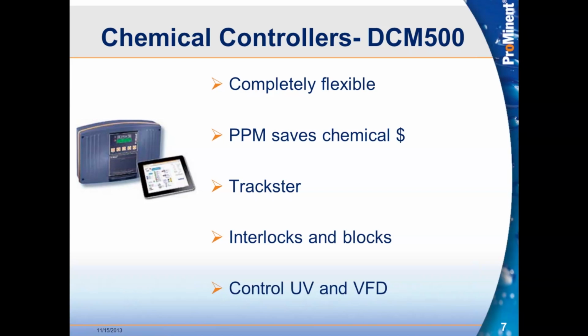Trackster auto poll allows us to, basically, I don't know if there's an upper limit, but let's say we have 30 controllers scattered across a metro area. Trackster running in the background on a computer somewhere can simultaneously watch all those controllers and reach out and grab a data packet as often as you want, and pull that data into the Trackster database. That does a few things for us. It helps us take electronic logs, to simultaneously watch 30 pools at the same time. Trackster can also text out and email out alarms, so that if something is occurring on one of those pools, we can automatically send that information out and alert whomever needs to know about it.